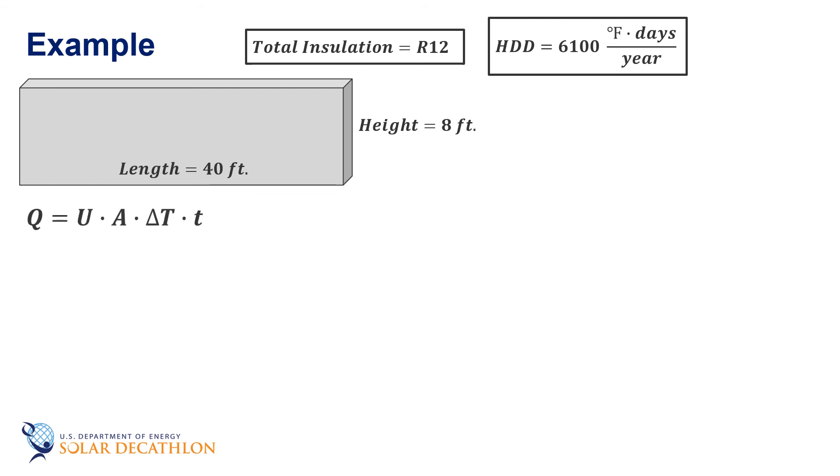Starting with our equation for heat transfer through the wall, or any other envelope component for that matter, we know that heating degree days is expressed as delta T and time. Area we can calculate and U can be replaced with 1 over R. The area is the length of the wall times its height, or in this case 40 feet times 8 feet, which equals 320 square feet.